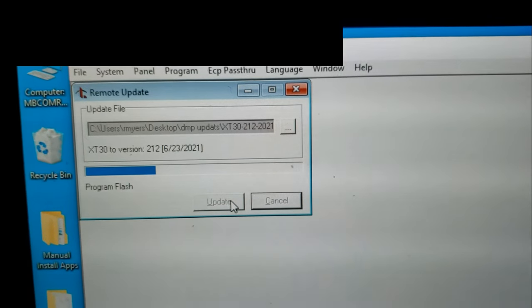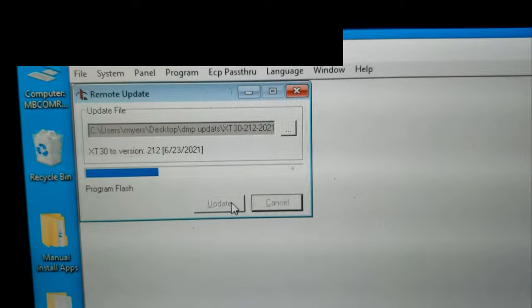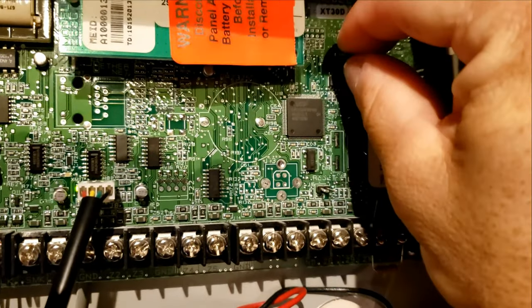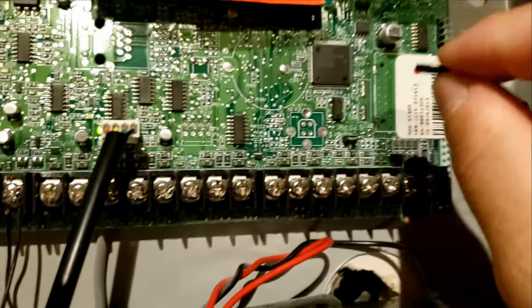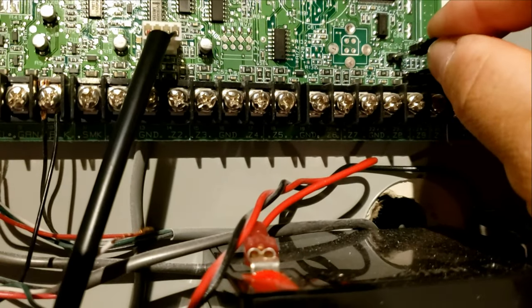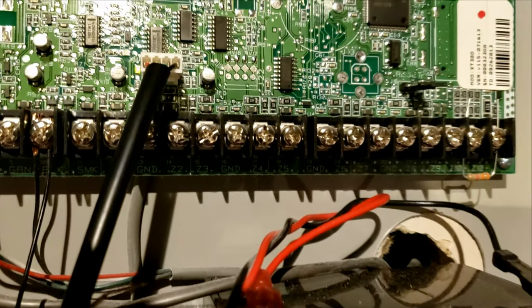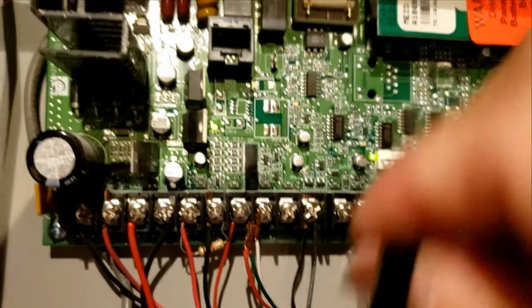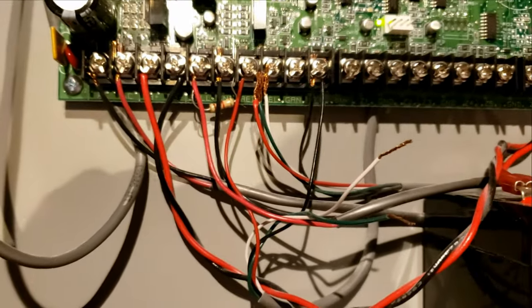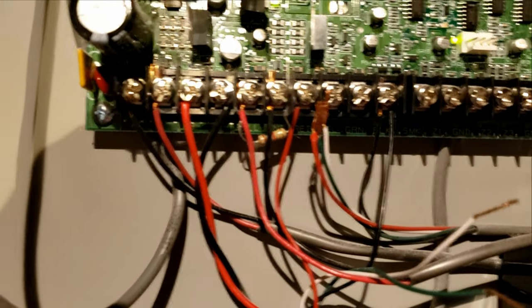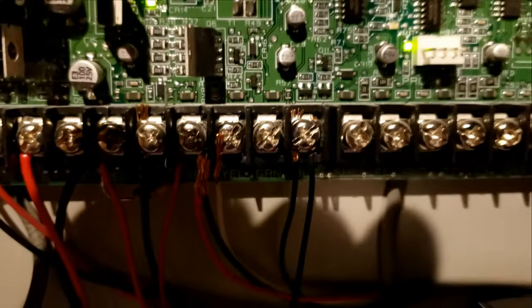So when you're done, take the load off, hit the reset, put one back on the leg, disconnect your 399, plug the keypads back up, power the panel down, and swap the cell card. You're done.